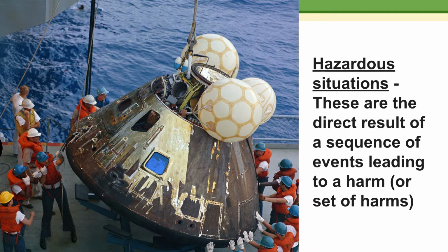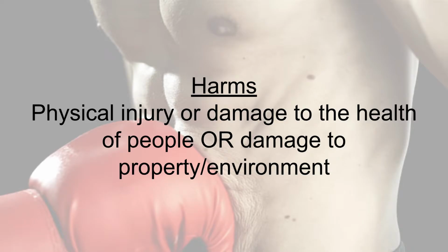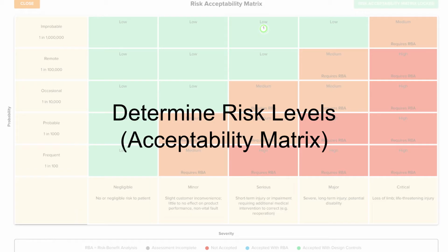The patient may or may not end up with an infection, but this is a hazardous situation that could lead to an infection. And so a harm, which is physical injury or damage to the health of people or damage to property and environment, in this case, would be an infection that results from a bacterial contamination of the aseptic field, resulting from the foreseeable sequence of events where a surgeon gets their glove caught in the surgical stapler and it tears. So that's a quick refresher of terminology.